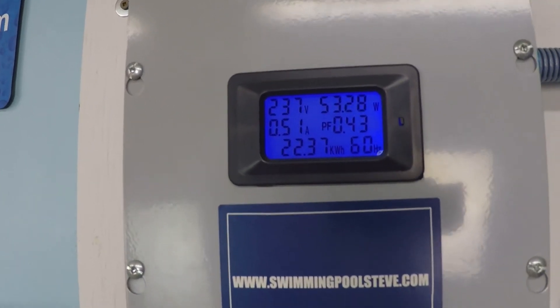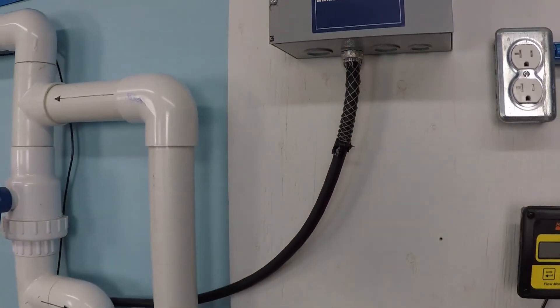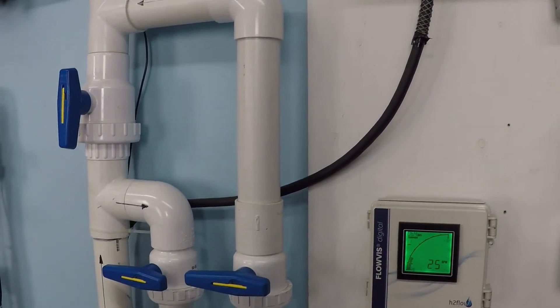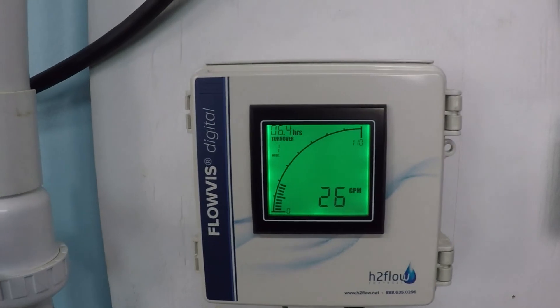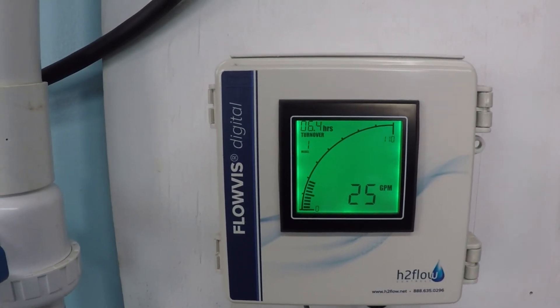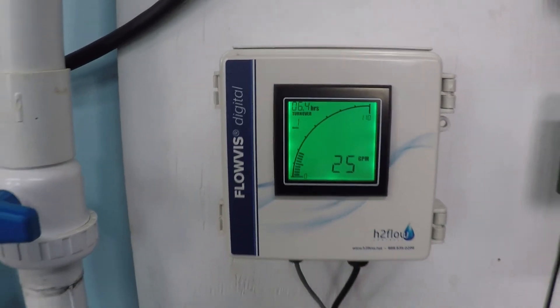53 watts of power consumption — have you ever heard of a 60 watt light bulb? We don't really use 60 watt light bulbs anymore; everything's more efficient than that with fluorescent lighting. But 53 watts is not a lot, and that's how much this pump is consuming right now. And that's what we're getting: 25 gallons per minute.